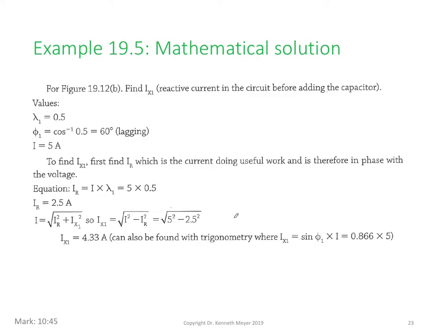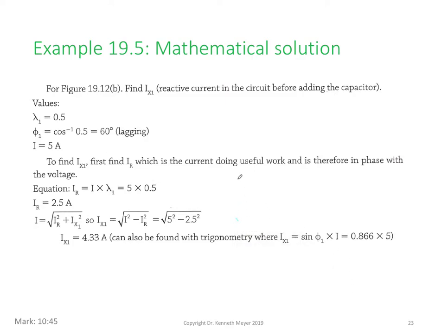So, give me a tick here, and I shall go to the pen. So if you remember, our triangles looked like this, and we're just getting I resistive on this side, and that side is just the power factor multiplied by 5, that is 0.5, will give us this side of the triangle. Once we have our 2.5, of course, we can then work out this side of the triangle, which is the current IX1. So the long side of the triangle.